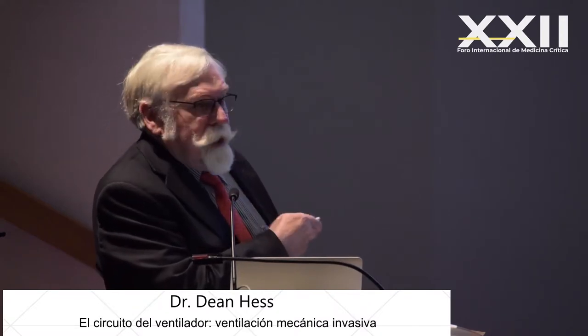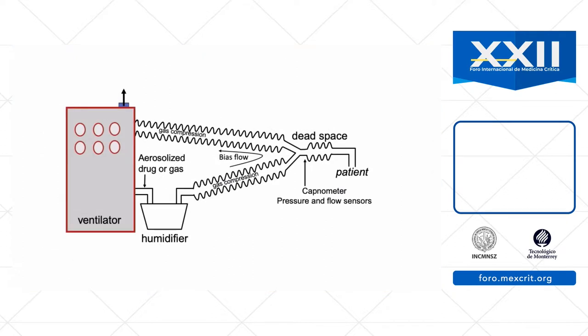There is typically a humidifier that is placed in line to warm and humidify the gas, because the gas delivered from the ventilator is a very dry and often cold gas. There are various ways that we can humidify the gas, either with passive or with active humidifiers.